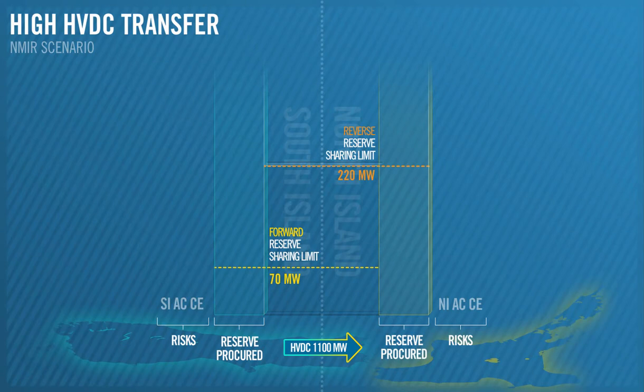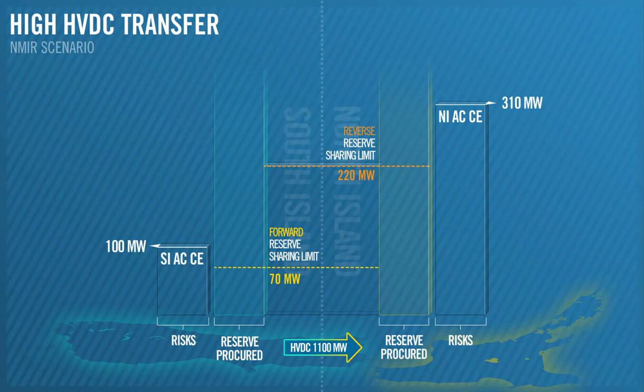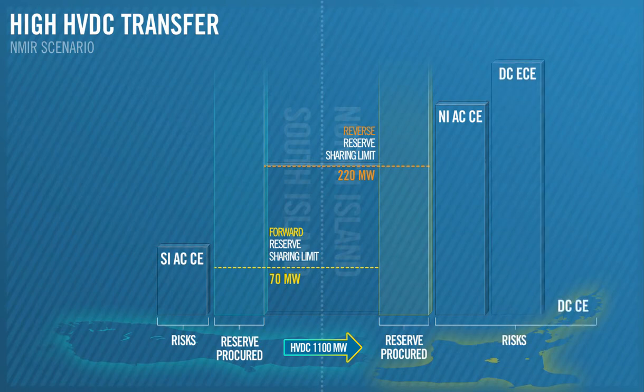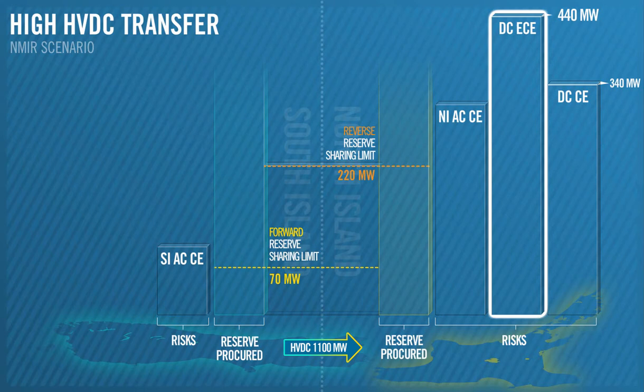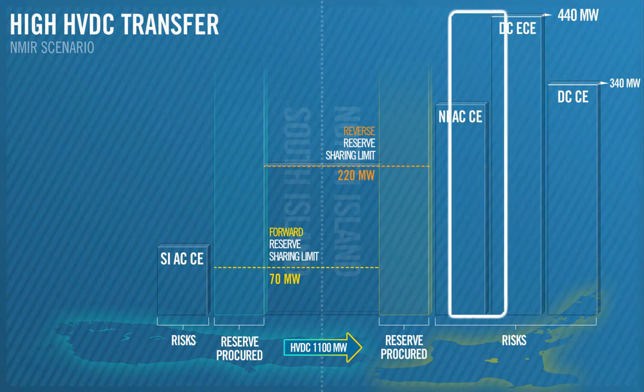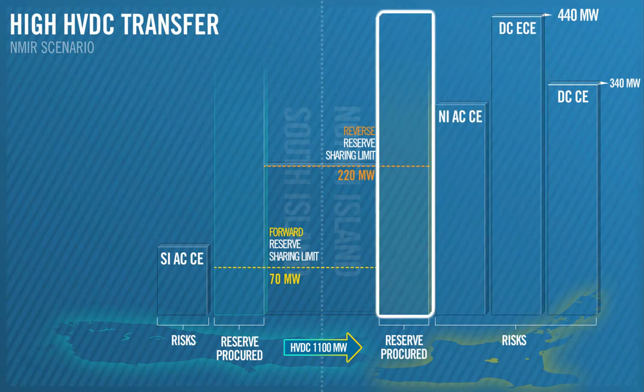Our AC risks are similar to previous scenarios, at 310 megawatts for the North Island and 100 megawatts for the South Island. But due to the high energy transfer across the HVDC, our DC risks become 440 megawatts for the DCECE and 340 megawatts for the DCCE. The DC risk must be covered by the reserve procured from the receiving island, in this case the North Island.